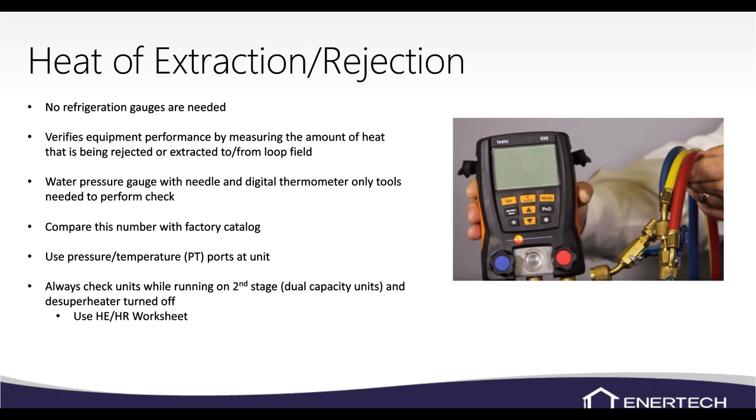We recommend always running the unit in second stage and doing the calculation in second stage. Some manuals have part-load information, but second stage is always recommended. Also turn the desuperheater off — the newer YT unit has a switch on the side of the control box to turn it off; if you don't have that switch, you can disconnect the pump.